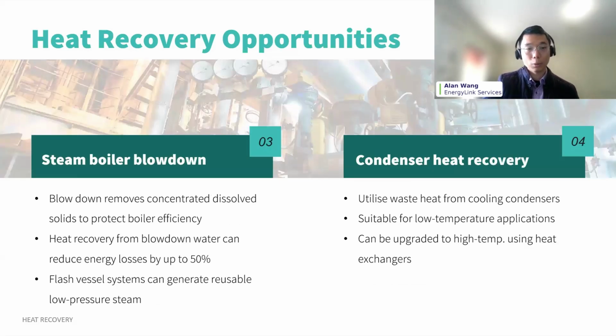And number 3, we've got the boiler blowdown, which is another major opportunity in steam boilers, especially operating, say, 10 to 15 bar. Blowdown water could be discharged at near saturation temperature. And instead of venting this energy, we can recover it through a flash vessel, generating low pressure flash steam, say around 3-4 bar, which can then be reused in other process or heating loops. This will then reduce energy losses from the blowdown.